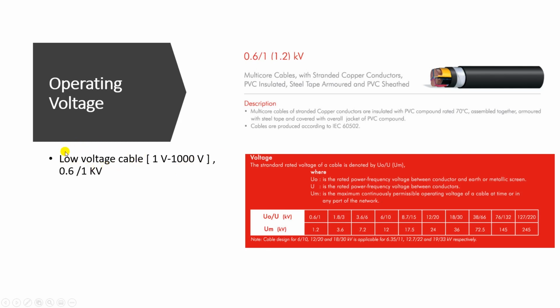An example of this cable is 0.6/1 kilovolt. Now what does this mean? If you open any catalog for cables, you'll find that this, for example, is a low voltage cable, a three phase and neutral. This cable operates at a voltage 0.6/1, and between two brackets 1.2 kilovolt. What does this mean? The first number represents the line to ground voltage, the voltage between a conductor or the phase and the ground. This is the phase voltage at which it operates. The 1 kilovolt is the line to line voltage, or phase to phase voltage, the voltage between two phases. And 1.2 kilovolt is the maximum voltage at which the cable can operate.